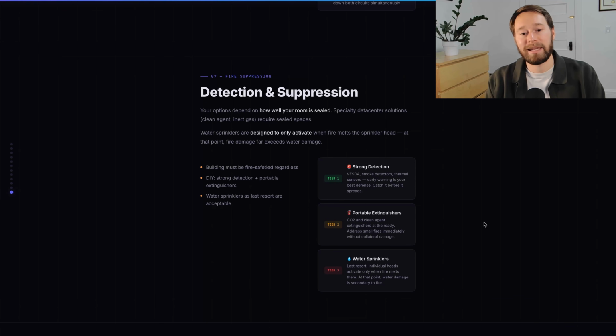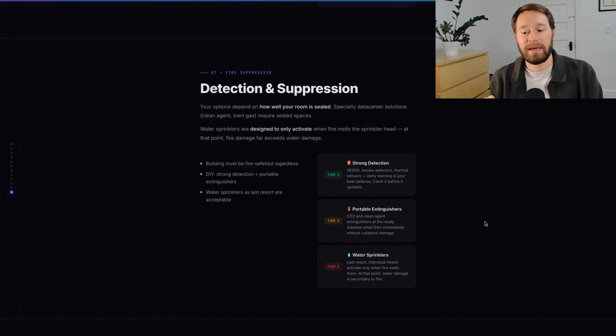But the reality is that if you're doing a data center in a warehouse, the containment and airtightness of your facility is going to be really low. And what that means is a lot of the data center fire suppression solutions that use inert gas or CO2 flooding, which require an airtight room to actually be effective, you can't really use.